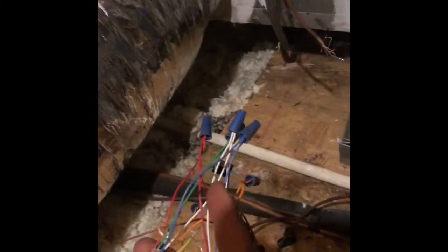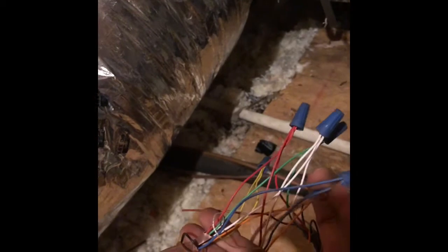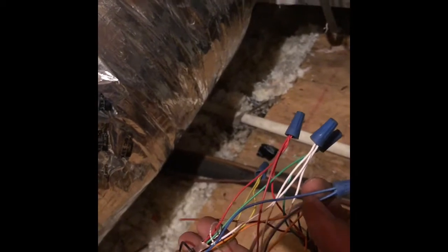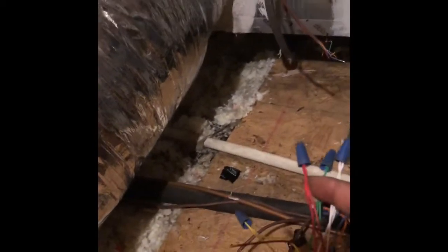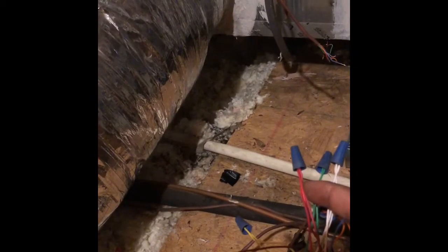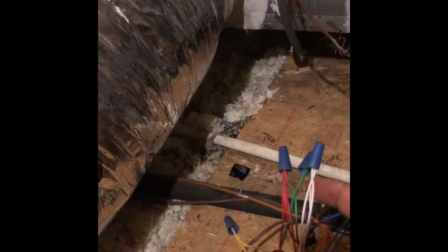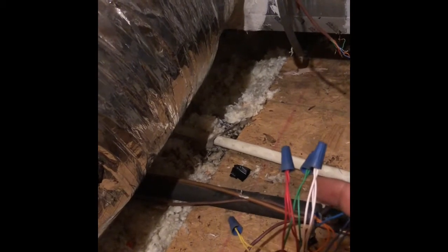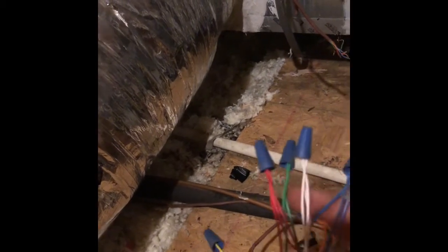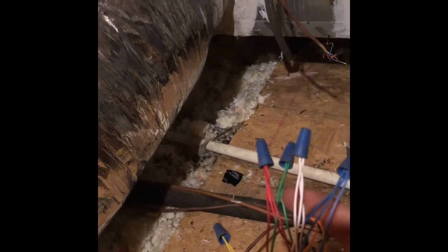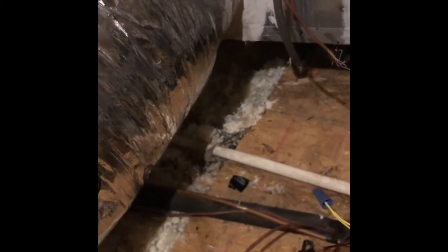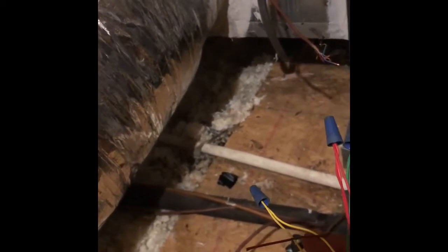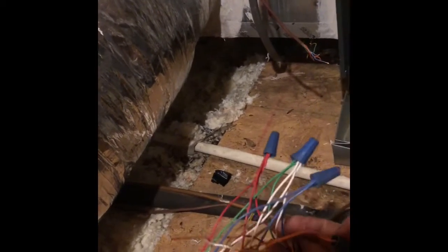So this is coming from the zone board here, and we have the blue which is our common going to our air handler and condenser, red going to the air handler and condenser, white going to the air handler and condenser, green going to the air handler, yellow going to the condenser, and orange going to the condenser.